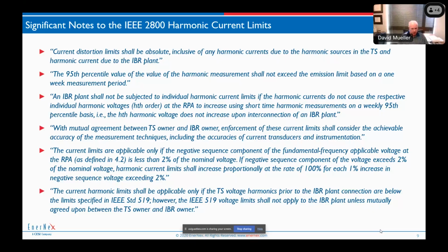An example of something that I do like is the third bullet, where it says an IBR plant shall not be subjected to these limits if the harmonic currents do not cause a problem. They do not cause the individual harmonic voltages to increase. Okay, so basically, let's not worry about things that don't matter. So if we've got a high 11th harmonic current, but we find out we don't have an increase in 11th harmonic voltage, then we're still okay. So I think that's an important exclusion, if you will, to be considered. And there are some other ones, and I'm not going to go through all those today.